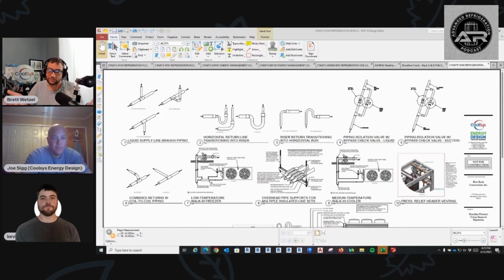But the labor. Yes. You have to have a cat that's gonna weld all that. Well, here's one thing that we do. We get the OEM to furnish all these valve branches to the field. Oh, so you just sweat one time, sweat another time, you're done. Yeah, they always come all field built. Yep. Got it. Yeah, and that's why we put the detail in our drawings. That allows the OEM to build them to what we need, basically. All right. I learned some stuff.